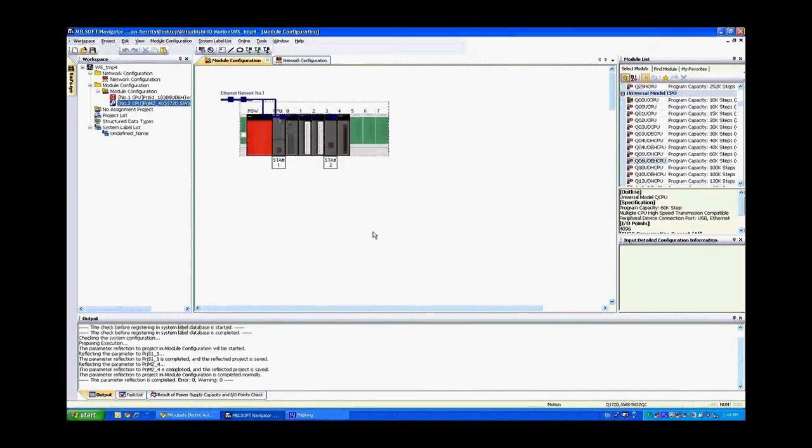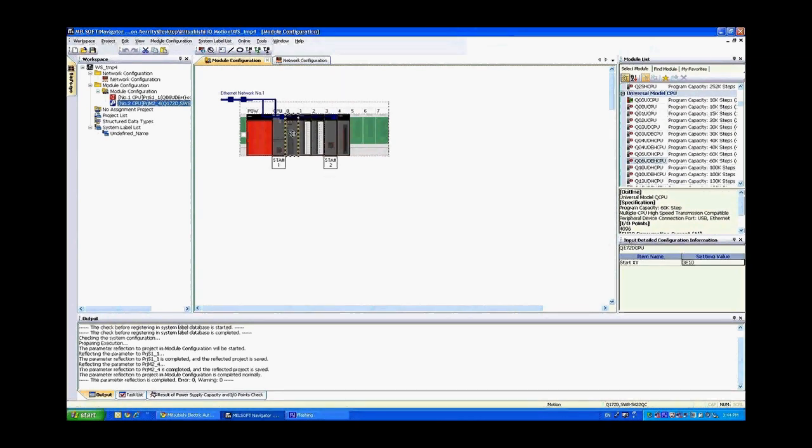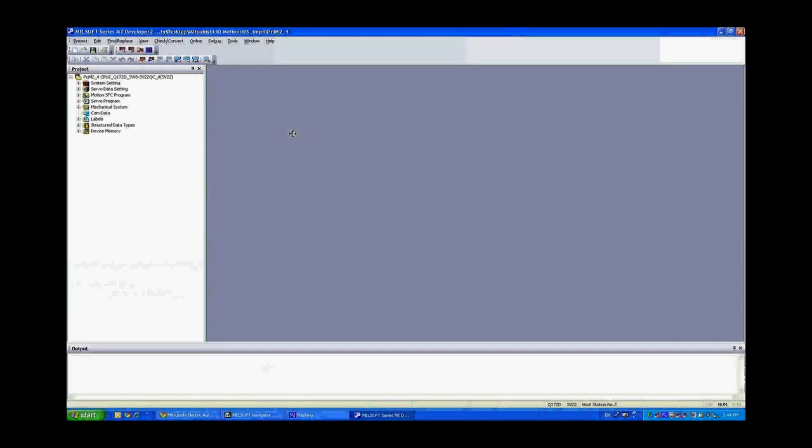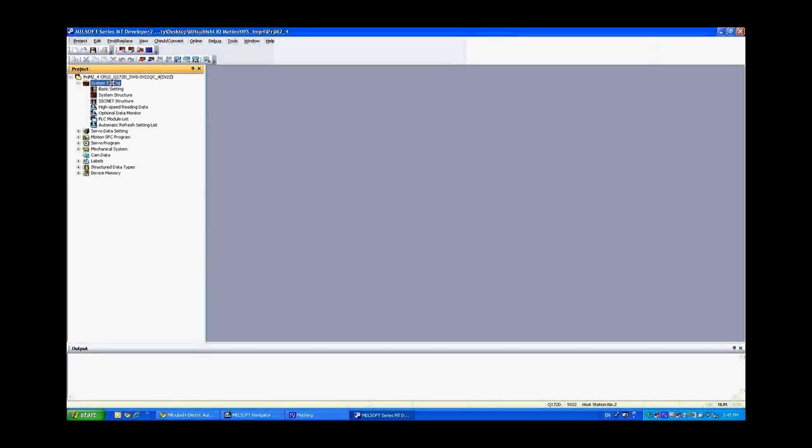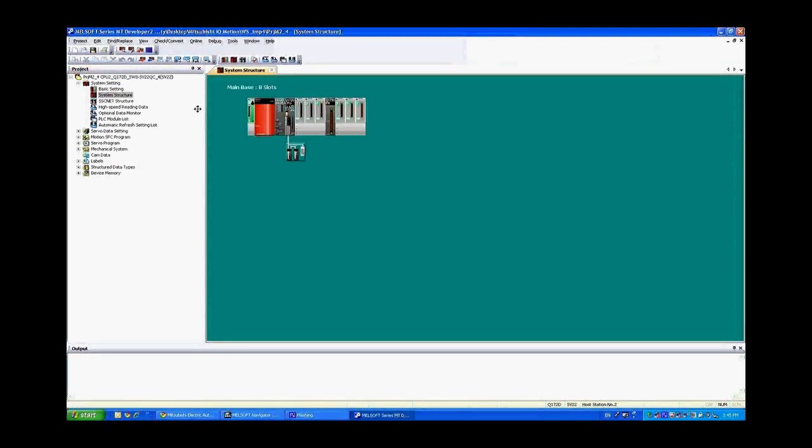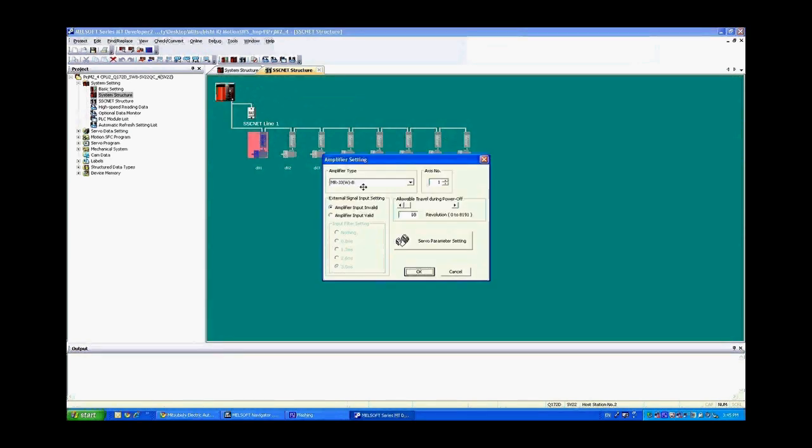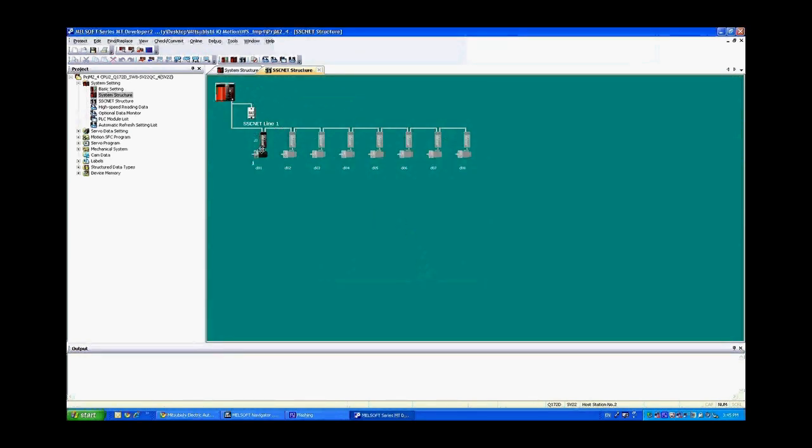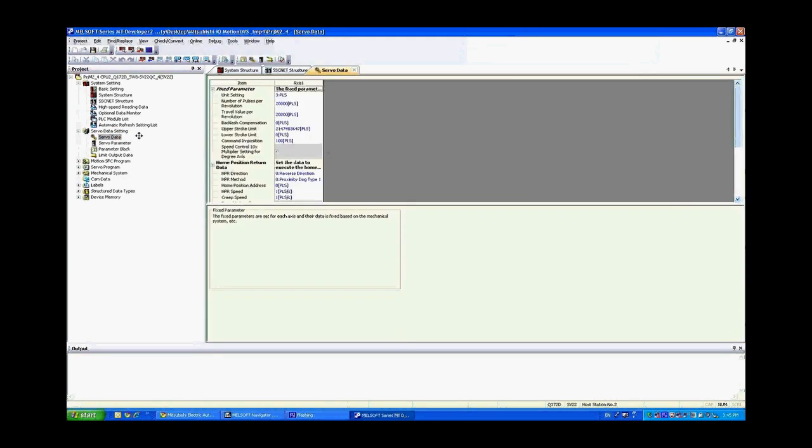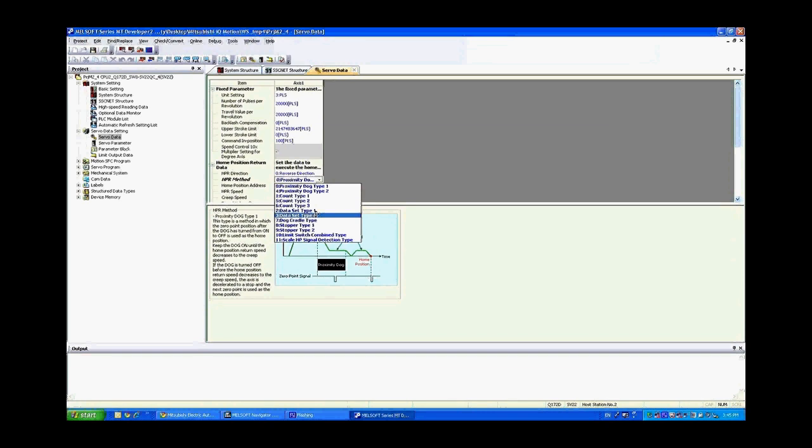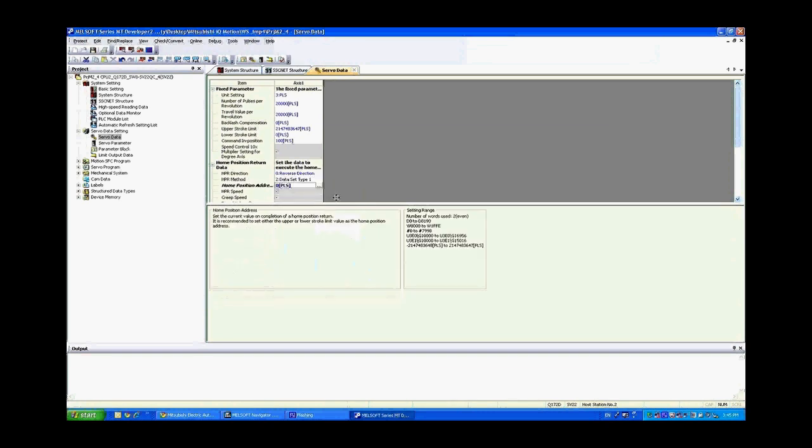And now that we've downloaded the OS into the motion controller we can go ahead and double click on the motion controller and that will launch MT Developer 2 which is the programming environment for that controller. Inside of here the first thing you're going to want to do is go into the system setting. Go to the system structure and you can see here that this is the SSCNET line. Go ahead and just configure one axis for now. Go ahead and say OK. And there you have a J3 series amplifier configured. And then in the servo data setting go ahead and click on servo data and we're going to change the home method to a data set type 1. OK. That's going to avoid us having to use a limit from the amplifier.